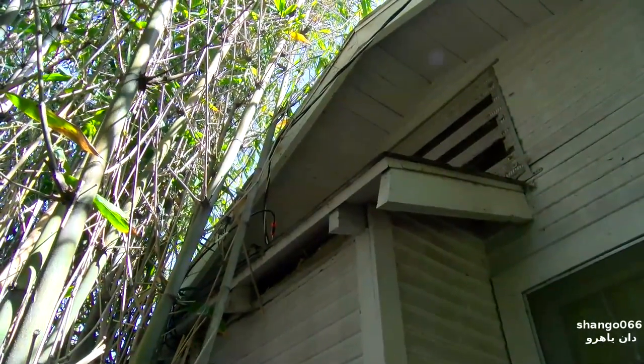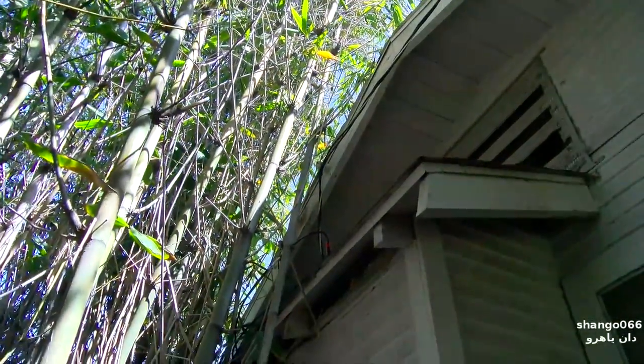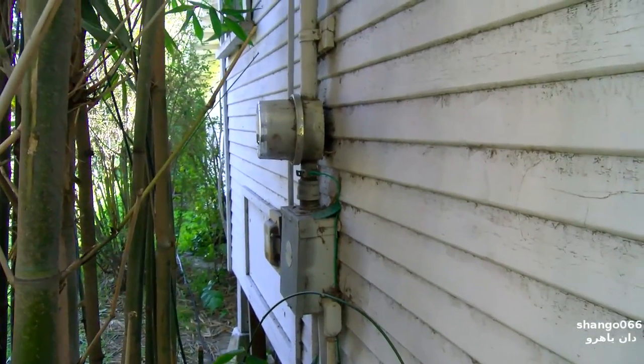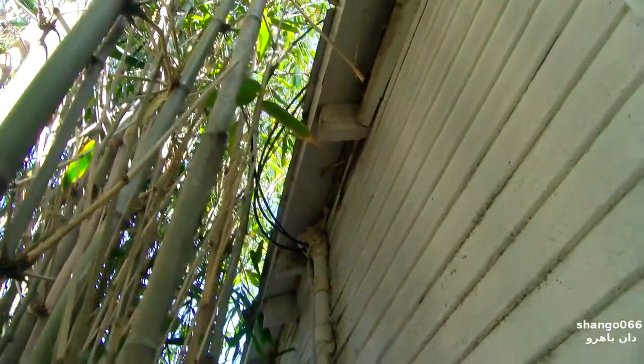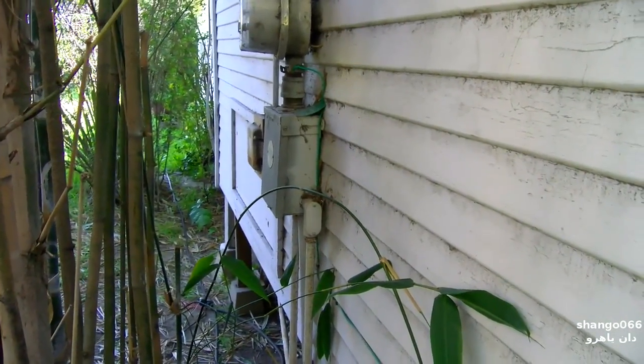To wrap this video up: they reinstalled the electrical service this morning and put in a new four gauge feed line — it was six gauge before. They went through and checked everything in here, measured all the voltages, and everything looked good. My wire measurements were just about perfect, so that's a good thing. Thanks for watching.